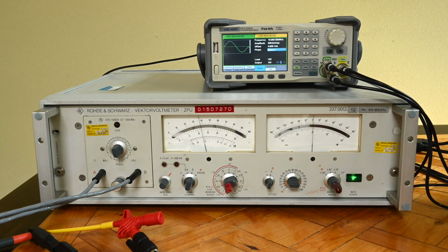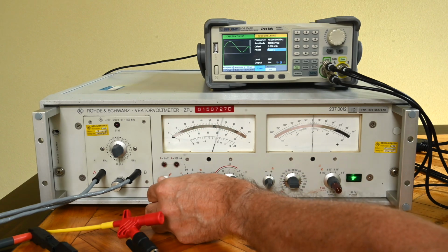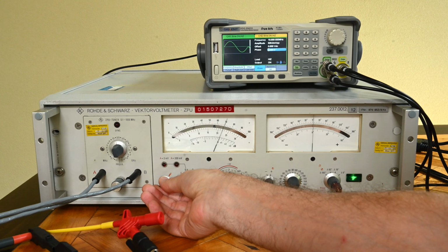Now, one more thing the device can do in terms of voltage measurement that I want to mention is that it can compare the two incoming voltages. What you would do is connect both of the channels to the same source, calibrate them, set the ratio to 0 dB on the dB scale, and then you can look at differences. Now let's do that. I'm just taking the signals as they come in. I'm going to use this manual indicator to put it on 0 dB.